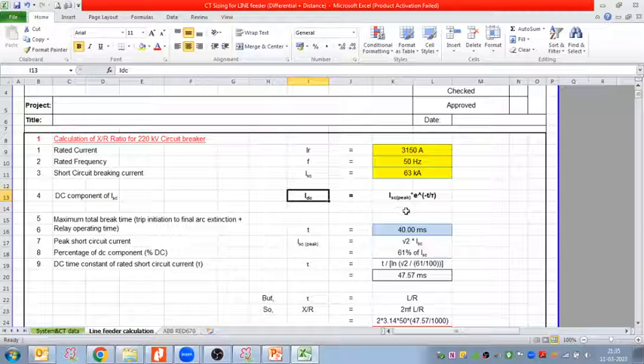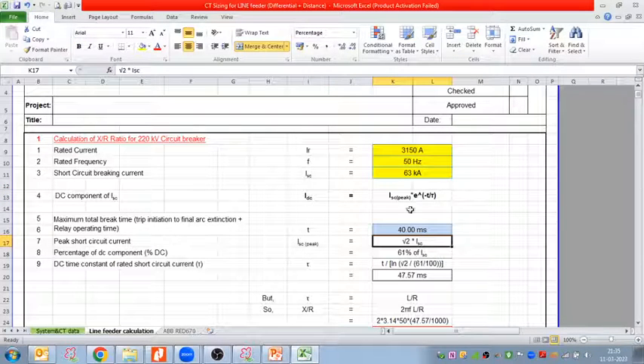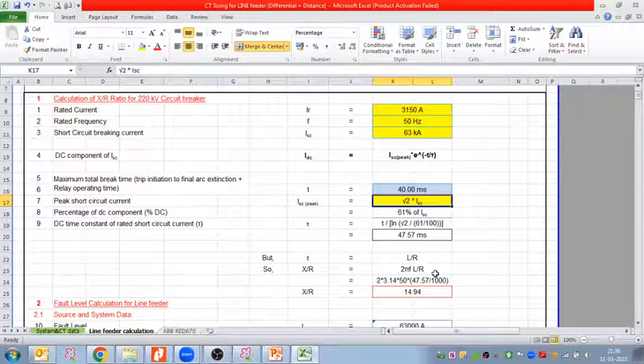Now, ISC peak is calculated as ISC times root 2. We know how to calculate the peak from the RMS value: to convert RMS into peak, we multiply by the square root of 2. So we have done that here to find the ISC peak. Now e to the power minus t divided by tau. T is my circuit breaker opening time, that is, how much time is required to open the circuit breaker.